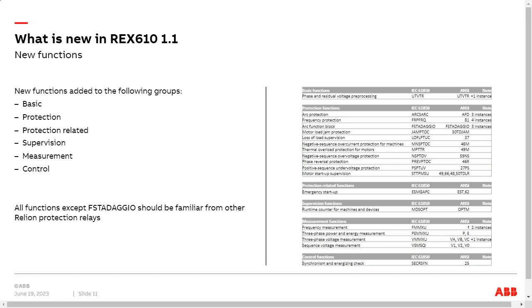Additionally, you can also see that we have the negative sequence overvoltage as well as positive sequence undervoltage protection there. In the protection related functions, we have the emergency startup, of course, that's for the motor application, and then in the supervision functions, we have the runtime counter for machines and devices. And then in the measurement functions, of course, we now have the frequency measurement as well as the three-phase power and energy measurement, and then the three-phase voltage measurement, the addition of one instance I already mentioned, and then we have the sequence voltage measurements. So as said, if you're familiar with Relion devices, all these function blocks should be familiar to you, except this ARC function block that I will present on upcoming slides.